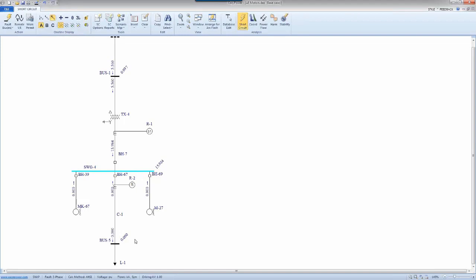We go through the same iteration and calculate the bolted fault current. Let's say that iteration is from 0 to delta T. We calculate this current, calculate it from bolted fault current to the arcing current, calculate the current contribution from branches, and calculate the trip times for these guys. So now, let's say trip time of this guy is 5-cycle. This guy becomes 6-cycle. This becomes 2-cycle.